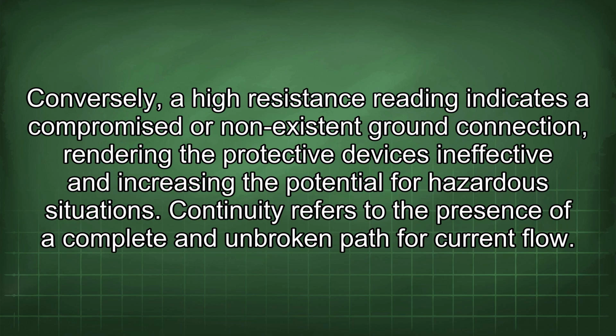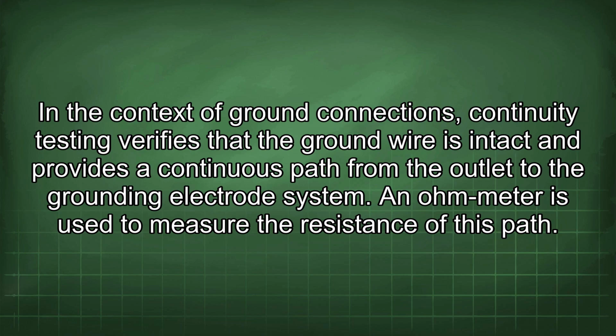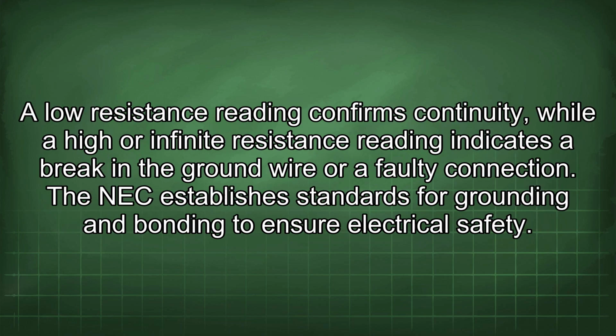Conversely, a high resistance reading indicates a compromised or non-existent ground connection, rendering the protective devices ineffective and increasing the potential for hazardous situations. Continuity refers to the presence of a complete and unbroken path for current flow. In the context of ground connections, continuity testing verifies that the ground wire is intact and provides a continuous path from the outlet to the grounding electrode system. An ohm-meter is used to measure the resistance of this path. A low resistance reading confirms continuity, while a high or infinite resistance reading indicates a break in the ground wire or a faulty connection.